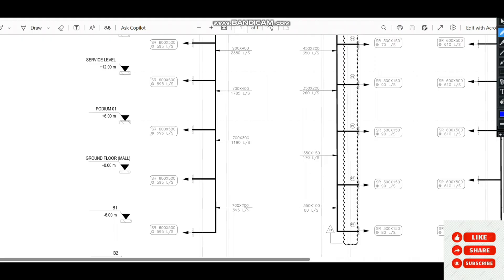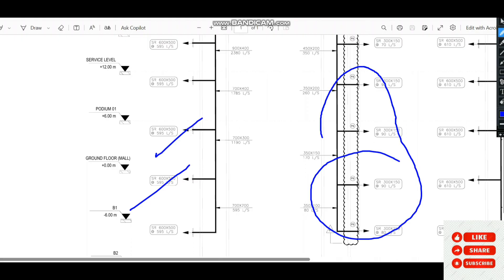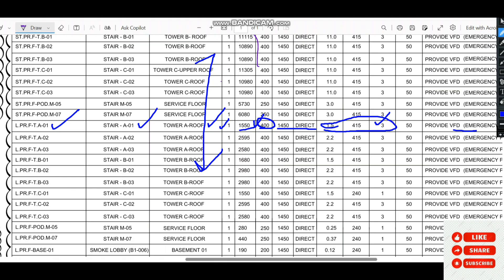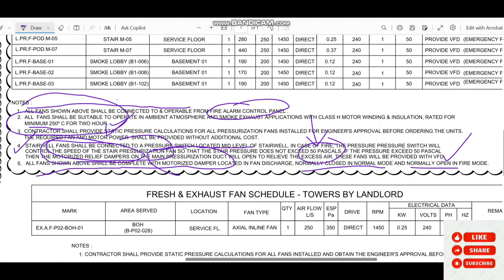Similar to the staircase, supply ducts pass through the lift shaft at all levels — basement 1, ground floor, and all floors above. From the schedule, the lift pressurization fan (tagged LPR-F-T-A-01) is located in Tower A roof, quantity one, with a flow rate of 1,550 liters per second and a specified external static pressure to be verified at shop drawing stage. It is a direct drive fan with three-phase supply, and a VFD shall be provided. No standby fan is required, but emergency power must be provided. Fire rating of 250°C for two hours is required, and the fan shall be controlled by the fire alarm control panel — requirements common to both lift and staircase pressurization fans.